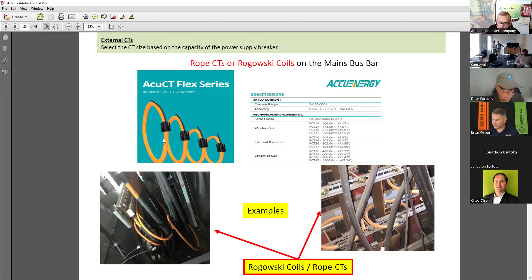But if you have a bus bar, most of the time the smallest one is enough because it is built to take the width of the bus bar, but you cannot put the tightest one simply because of the space available for your hands to go through. You may be wearing your gloves, you may be having your hazard equipment, you're wearing your shield, your helmet. So you use a bigger size to make it convenient for you to send the Rogowski coil to wrap it around the bus bar, even though you don't need a big diameter. You may go one size up or two sizes up to do it.